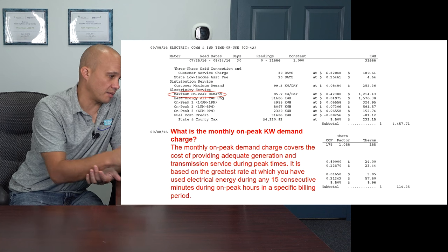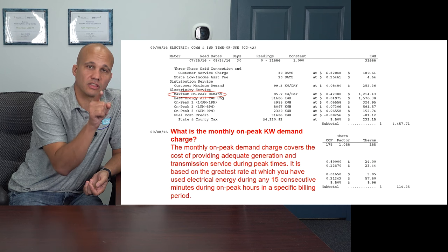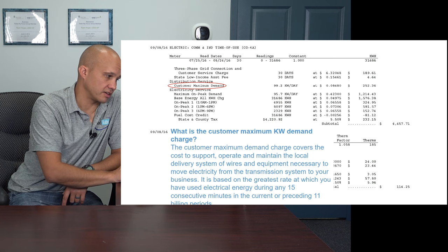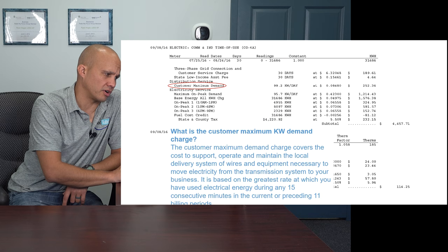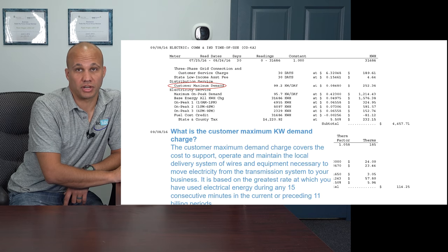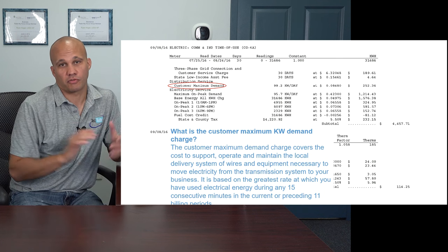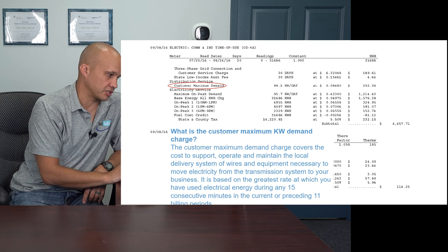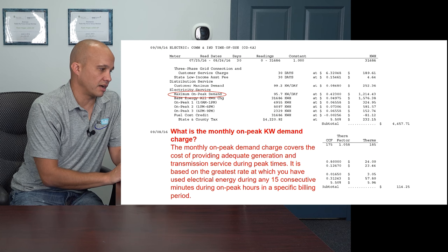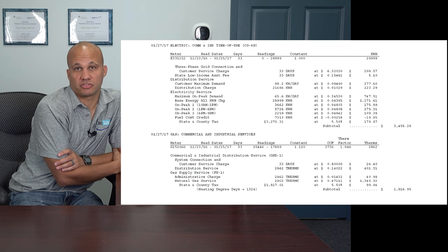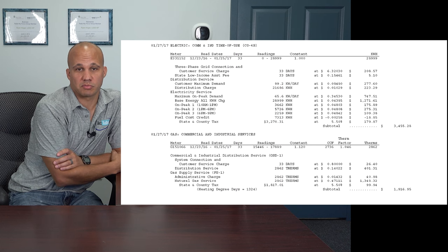Those demand peaks really add up and are impactful because they can last the whole year. Looking at a winter bill, that 99.2 KW distribution demand charge shows up on summer and winter — the exact same 99.2 — because it stays on there all year. It's the highest peak you had in any 15-minute window for the entire past 12 months. So if you make one mistake and put a bunch of loads on at the same time, you pay for it every single month for the whole year. The monthly electricity demand, however, was 95.7 KW in summer versus 65.6 KW in winter.